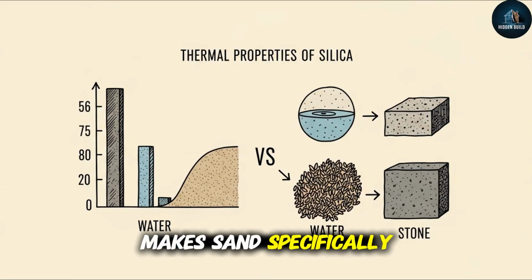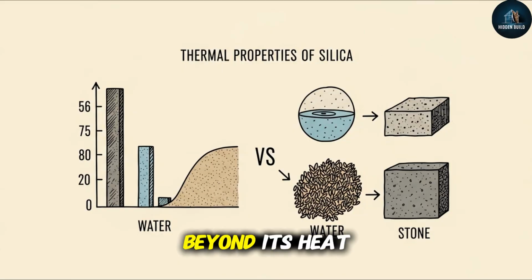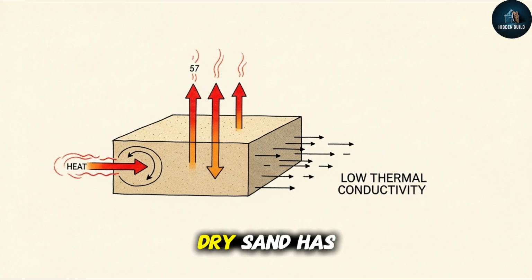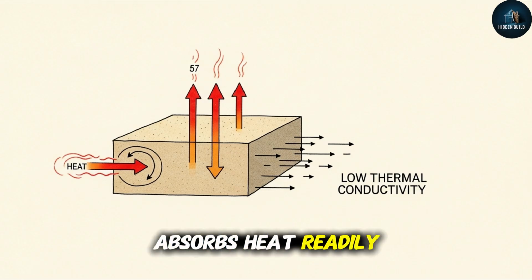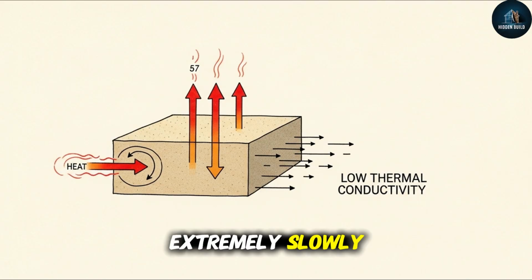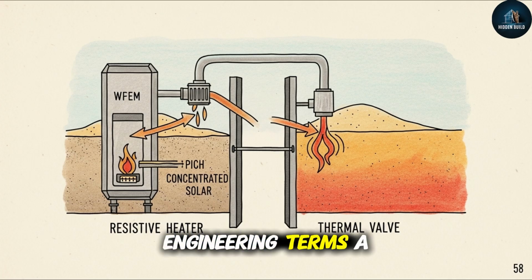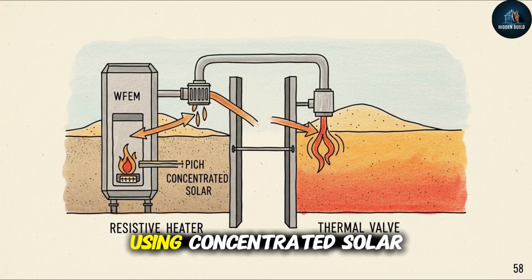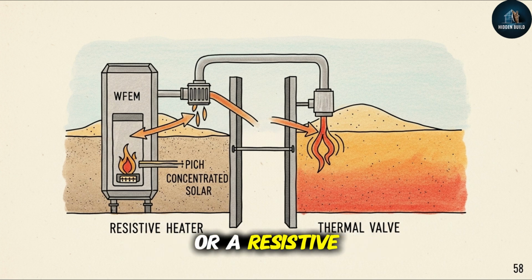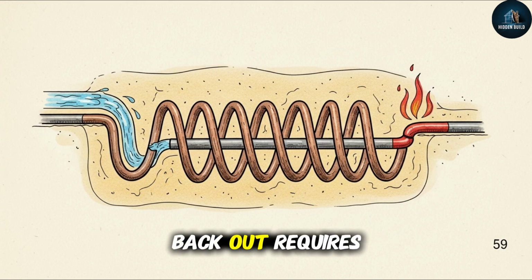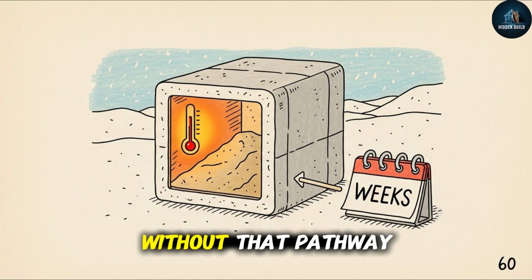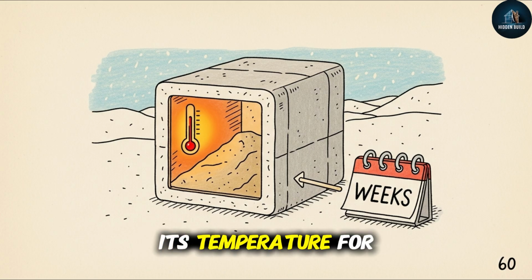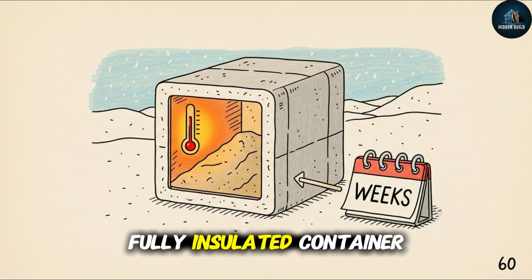Here is what makes sand specifically suited for this application beyond its heat capacity numbers. Dry sand has almost zero thermal conductivity. That means it absorbs heat readily but releases it extremely slowly. It is, in engineering terms, a one-way thermal valve. You can drive enormous amounts of energy into it quickly using concentrated solar or a resistive element. Getting that energy back out requires a designed pathway, a heat exchanger, a copper coil. Without that pathway, the sand holds its temperature for days, weeks, in a fully insulated container.